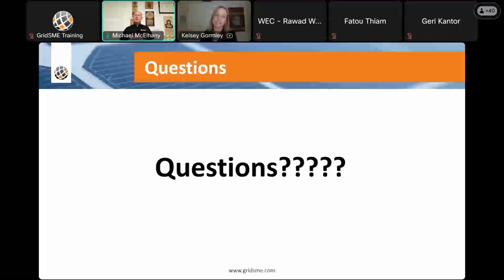So Kelsey's smiling because when I put together a deep dive on Appendix H, I was talking about EMT modeling and a lot of other things. There are other things that are happening within NERC that may drive us to a world of EMT modeling. In some of my conversations with inverter manufacturers, if we could provide an EMT model, a PSCAD model, they could turn the inverter settings around immediately because it is a direct one-for-one correlation with the inverter settings. From a PSCAD model for an SMA inverter or a Power Electronics inverter, it's a one-for-one. We haven't started having the conversations with clients yet, but eventually you do have to provide EMT models. It might be something to be thinking about earlier in the process because it might also help out the inverter settings from a bucket 3 perspective. Since he's not on, I'm not sure what additional changes he was referring to, other than in the way I answered the question.